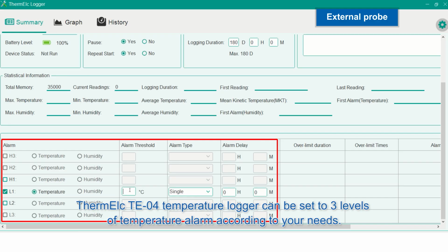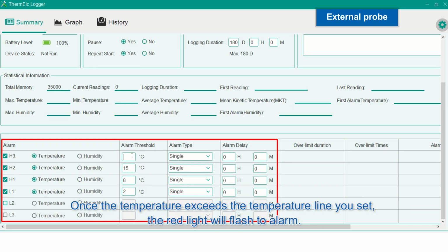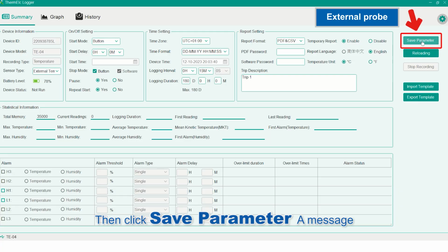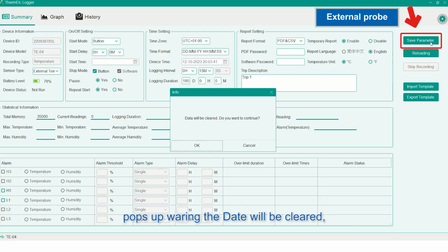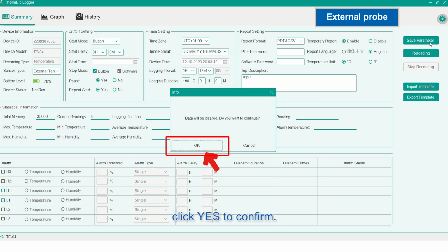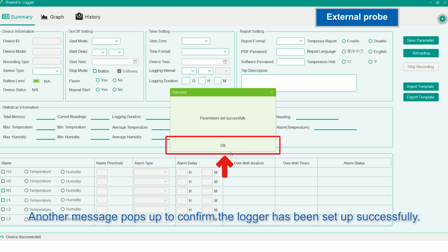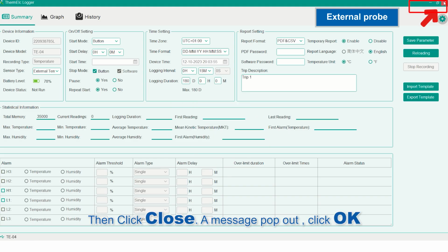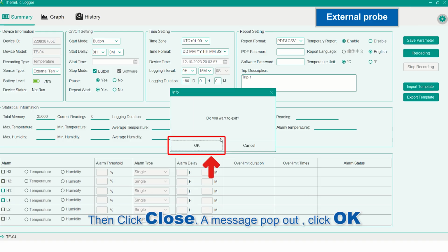The ThermElc TE-04 temperature logger can be set to three levels of temperature alarm according to your needs. Once the temperature exceeds the line you set, the red light will flash to alarm. Then click Save Parameter; a message pops up stating the data will be cleared. Click Yes to confirm, and another message pops up confirming the logger has been set up successfully. Then click Close. A message pops up, and click OK.